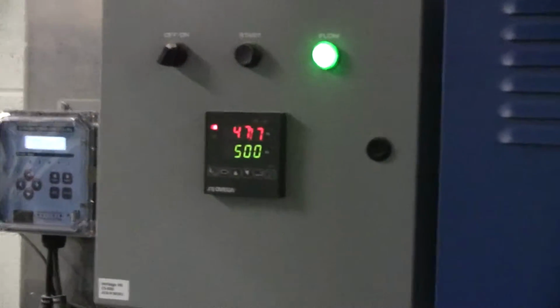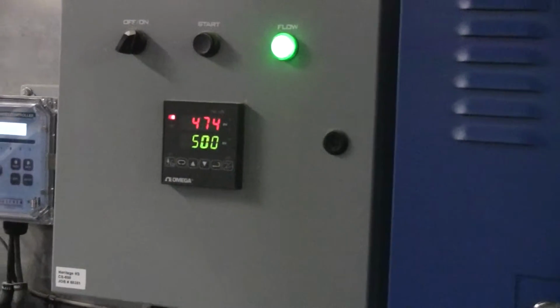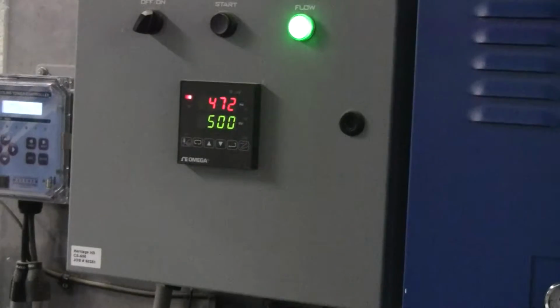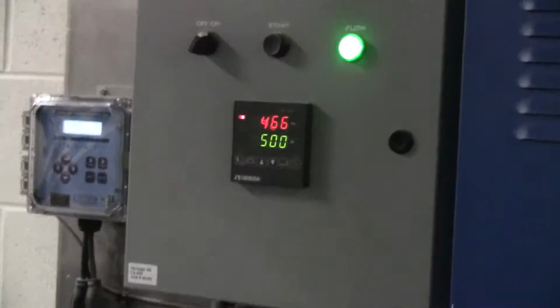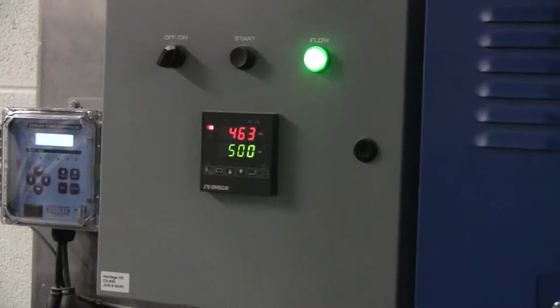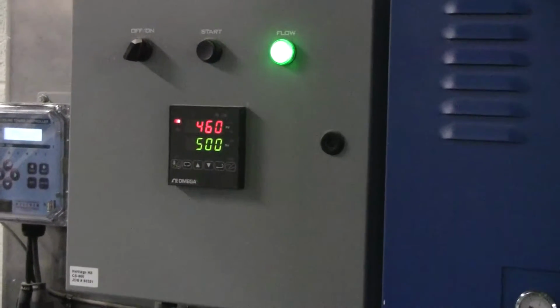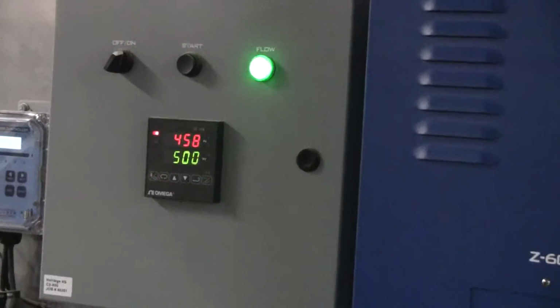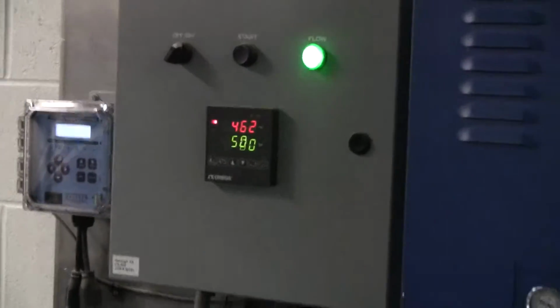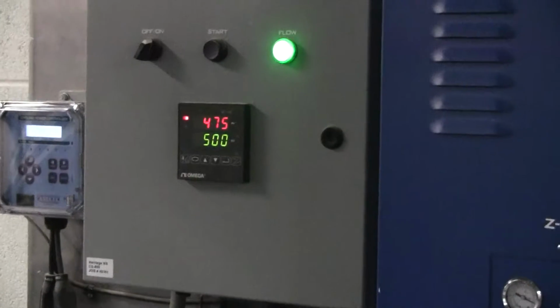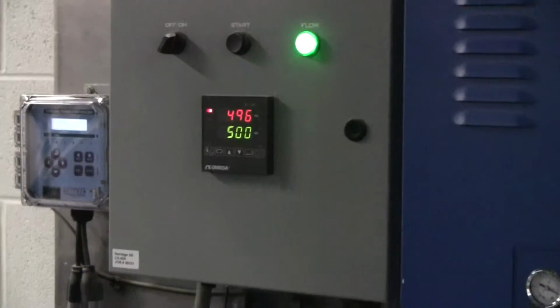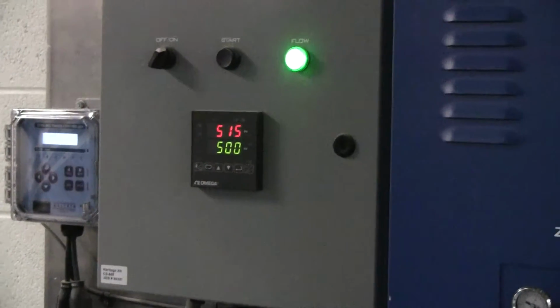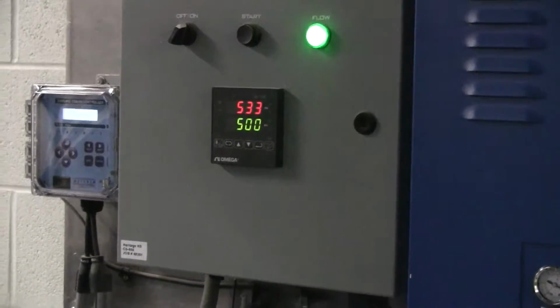As you can see, it receives a signal from the ORP probe. When it drops below the set point, it sends a signal to the generator to tell it to ramp up, produce more ozone so that we can protect the system, keep it clean. When it gets above the set point, it ramps the generator down so that we're not overproducing ozone. Strict control of how much ozone we put in the system is very important to protect the system, to make sure it's clean, and to protect it from overfeed.